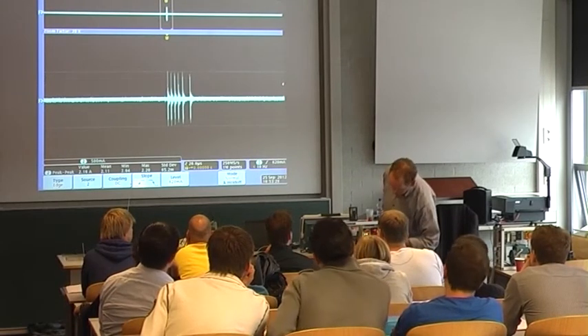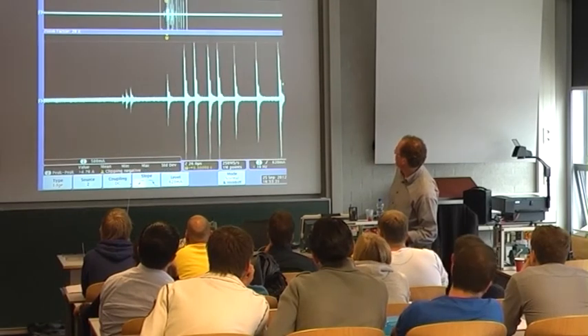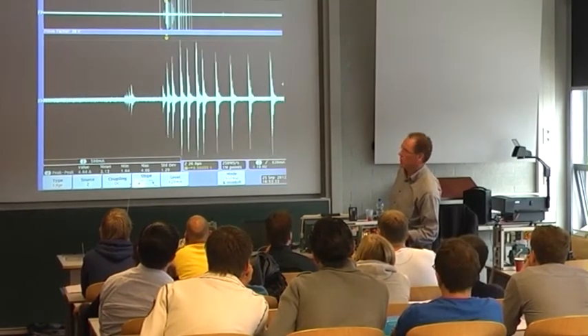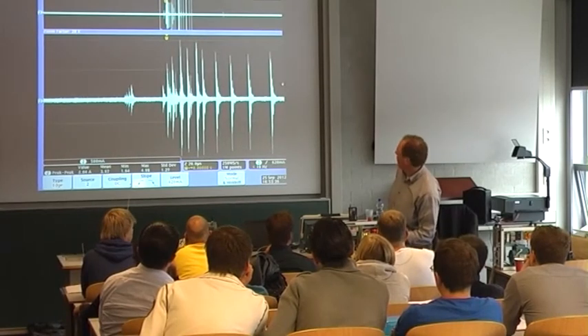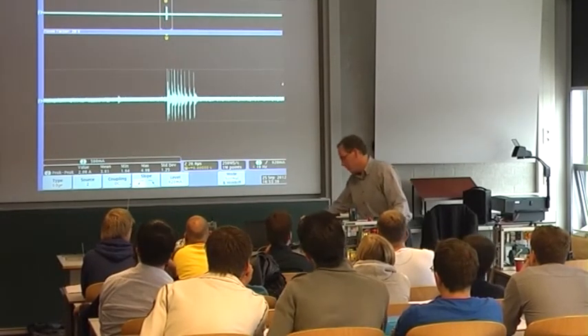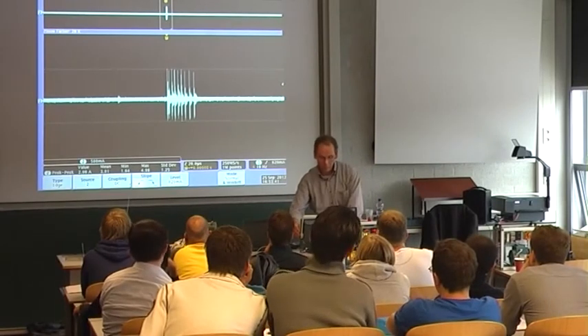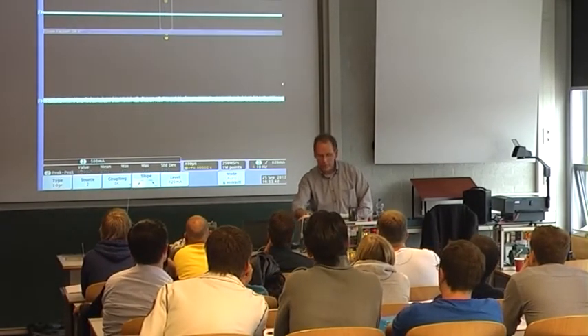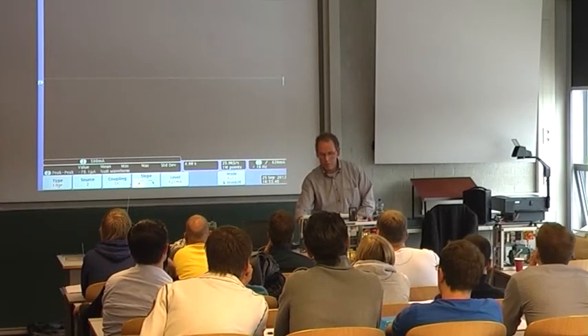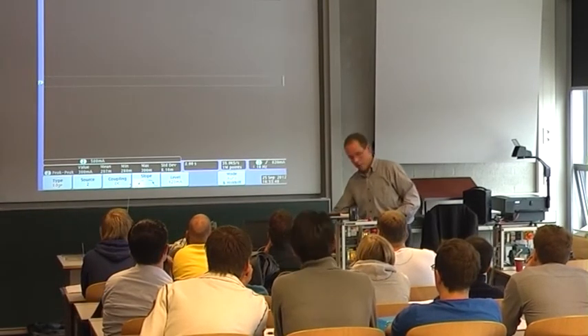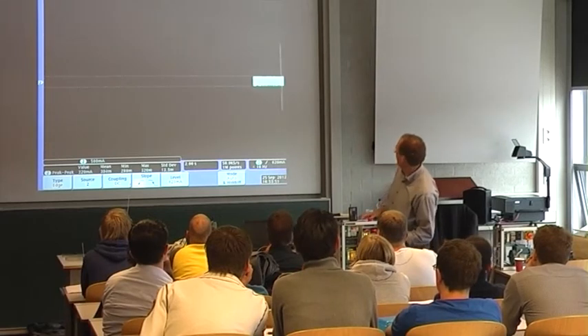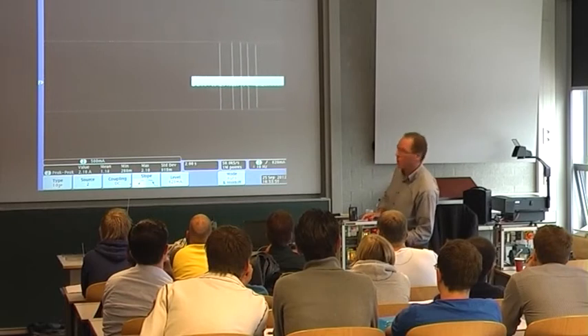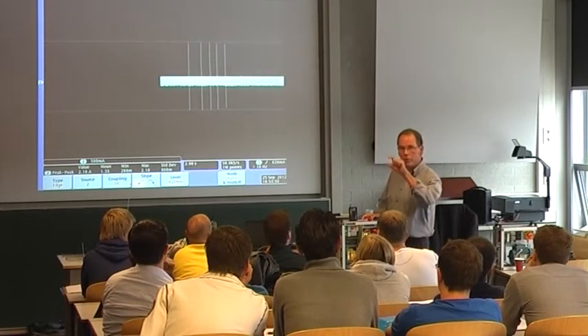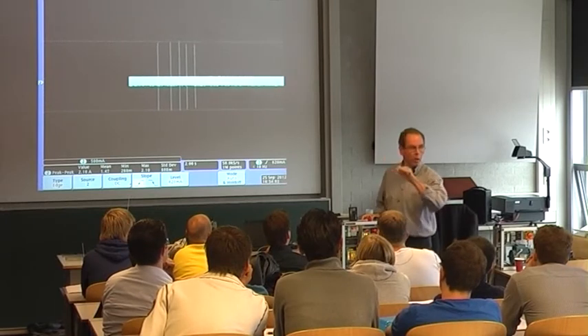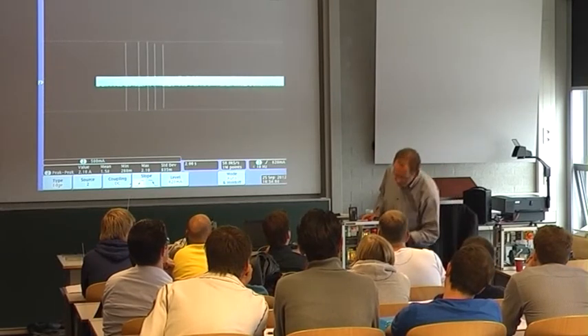Or with a circuit breaker on AC. Just to show the effect of a coupling/decoupling device, going back to this cable: switching off and on, a bit faster - off, on, off. Then the same valve with decoupling, an RC network - there's no noise. So it's a €1.50 decoupling device across the terminals, and it's not producing any noise.